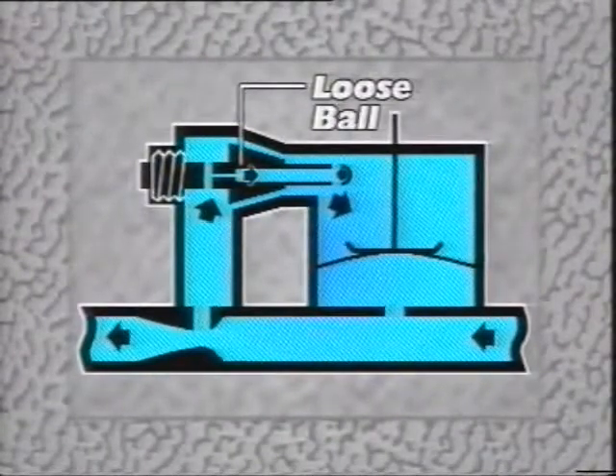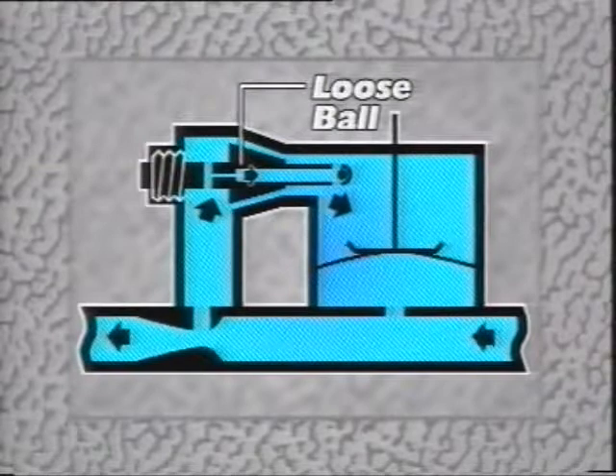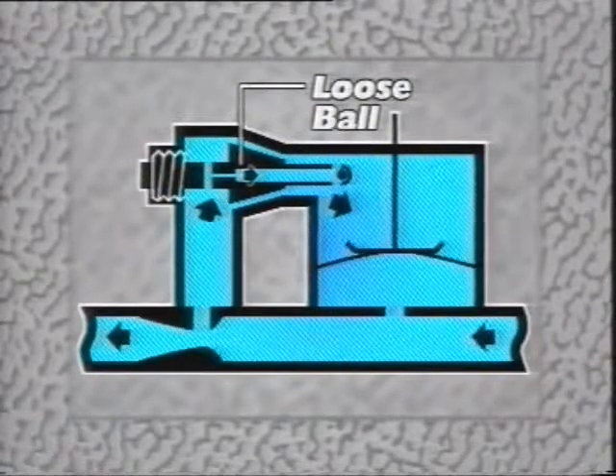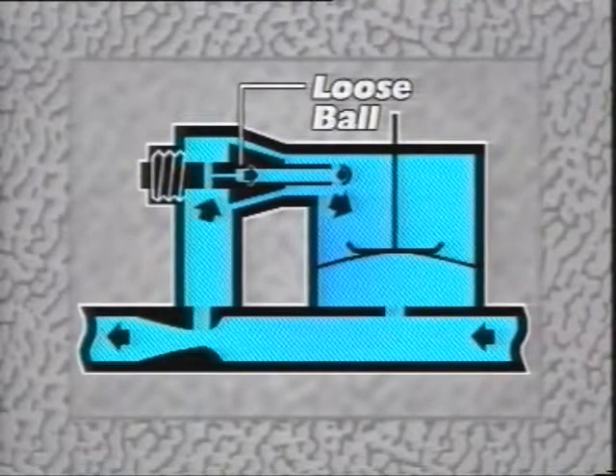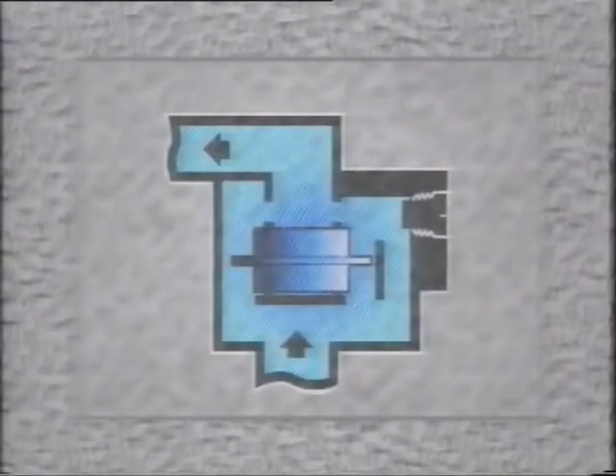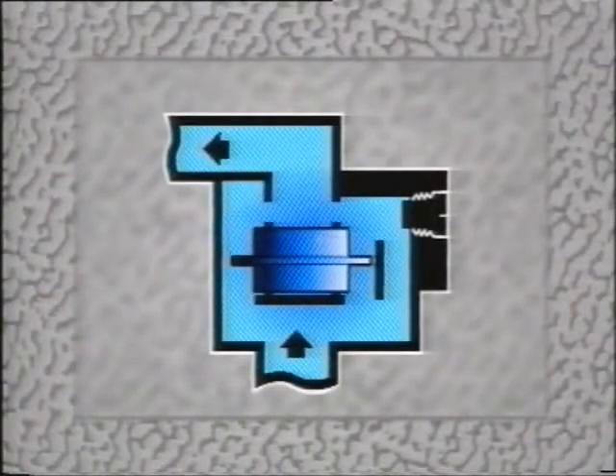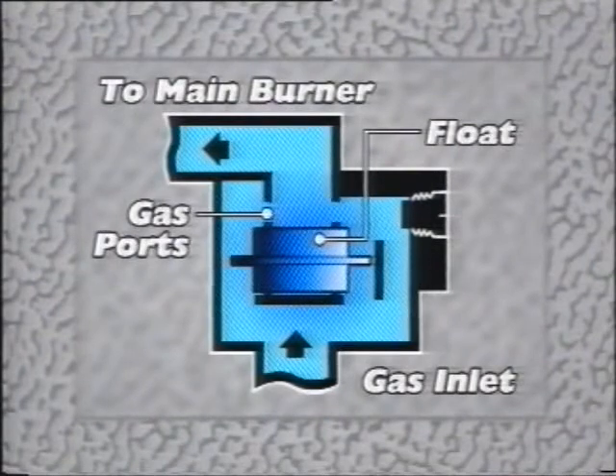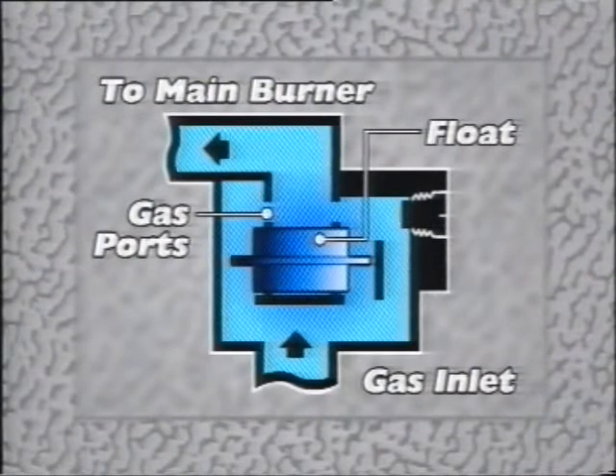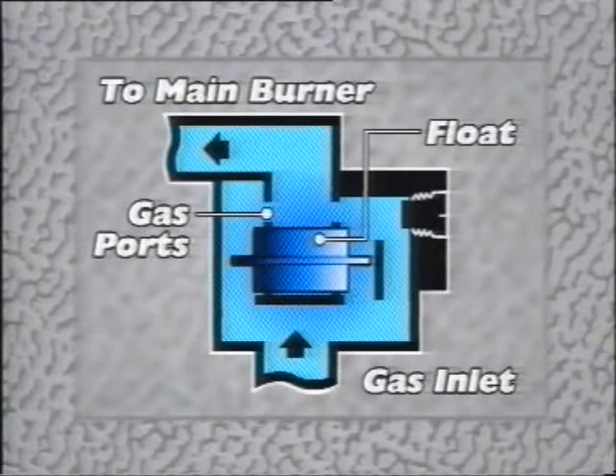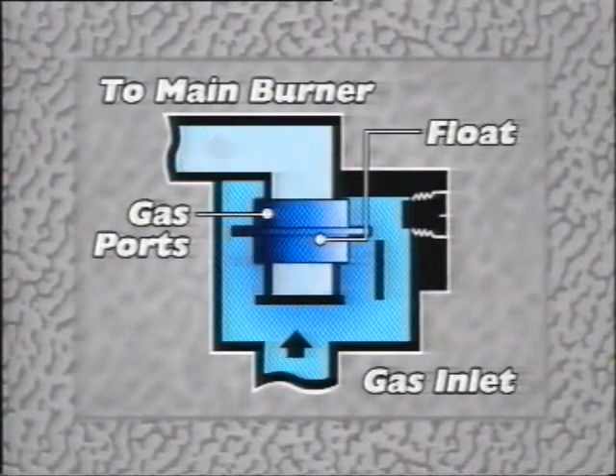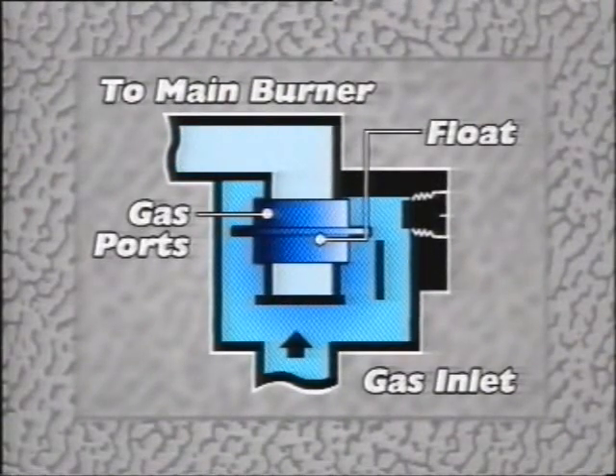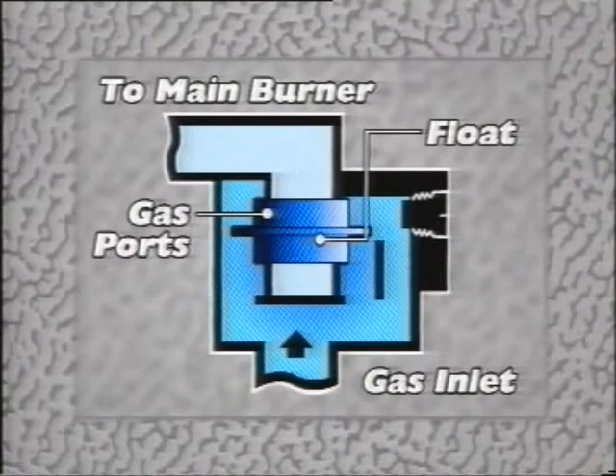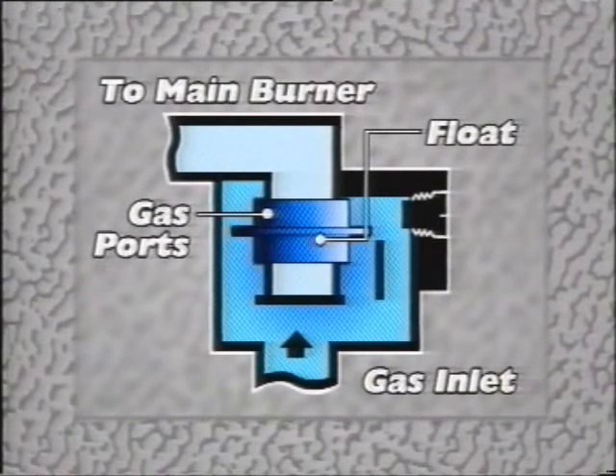When the valve's closing, the loose ball moves out of the orifice. The flow to the upper side of the diaphragm increases and the gas valve closes quickly. Thanks to this constant volume governor, the volume of the gas delivered to the burner doesn't vary. That means that instantaneous water heaters only need to increase or decrease the flow of water to control its temperature. The greater the flow, the lower the temperature, and vice versa.